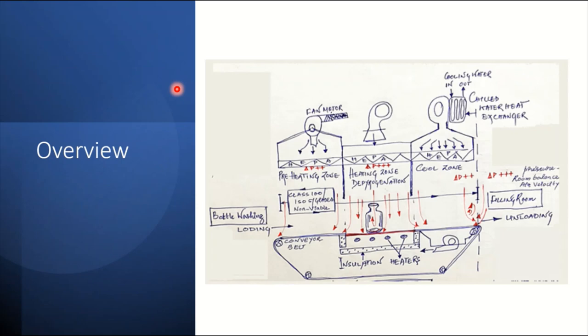If we explain this diagram, we should see that there are three zones: zone one, zone two, and zone three. The first one is called preheating zone where bottles after washing in the vial washing machine are loaded. It will initially dry the remaining water on the surface of the bottle and get preheated in this zone. Then it will enter into the heating zone or depyrogenation zone where the vial or intended packing material will be depyrogenated.